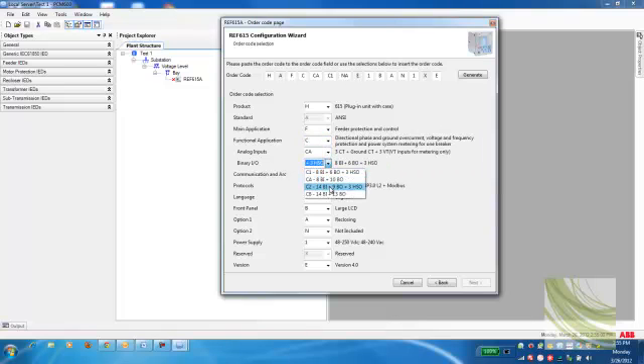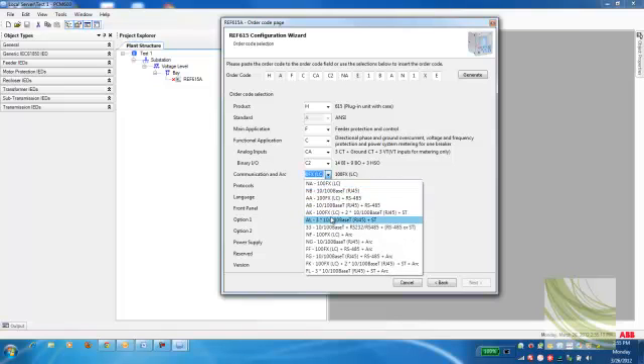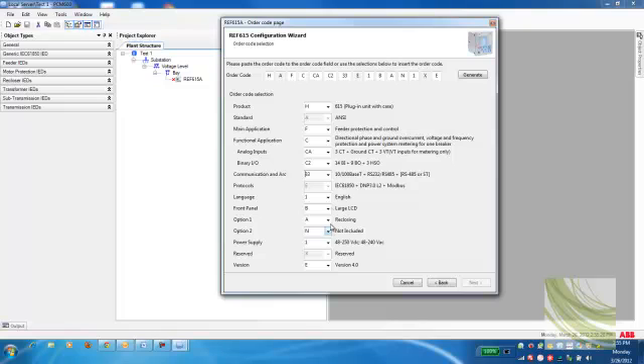I'll select here that we have 14 binary inputs and 8 binary outputs with 3 high-speed outputs. And then I'll also select the communication and the arc protection that we're going to need for this relay. For the time being, I'll just select the 10-100 base-T and the RS-232-485 with an ST connection.